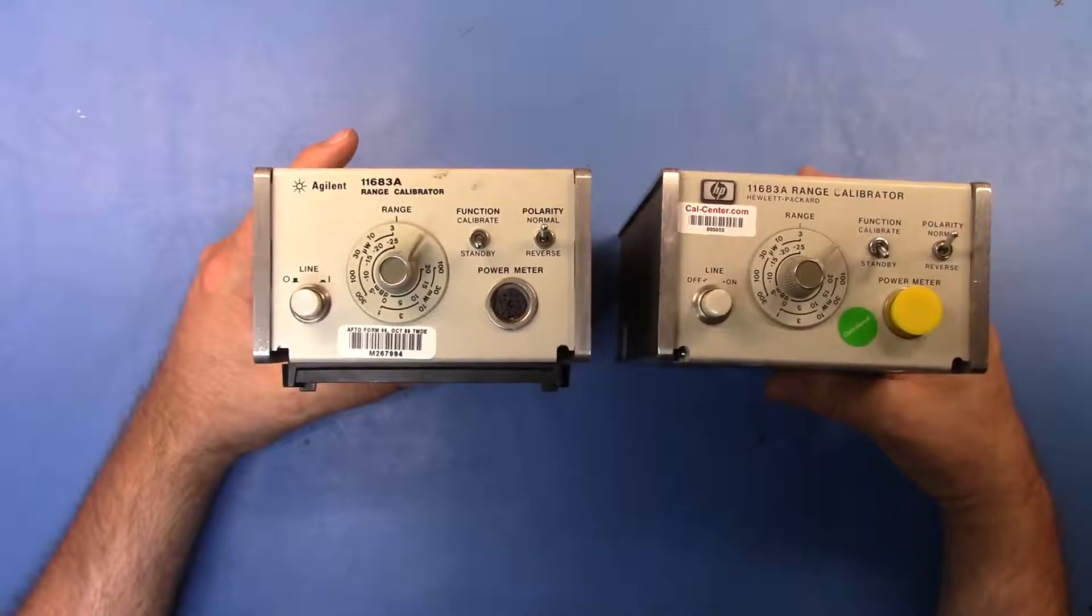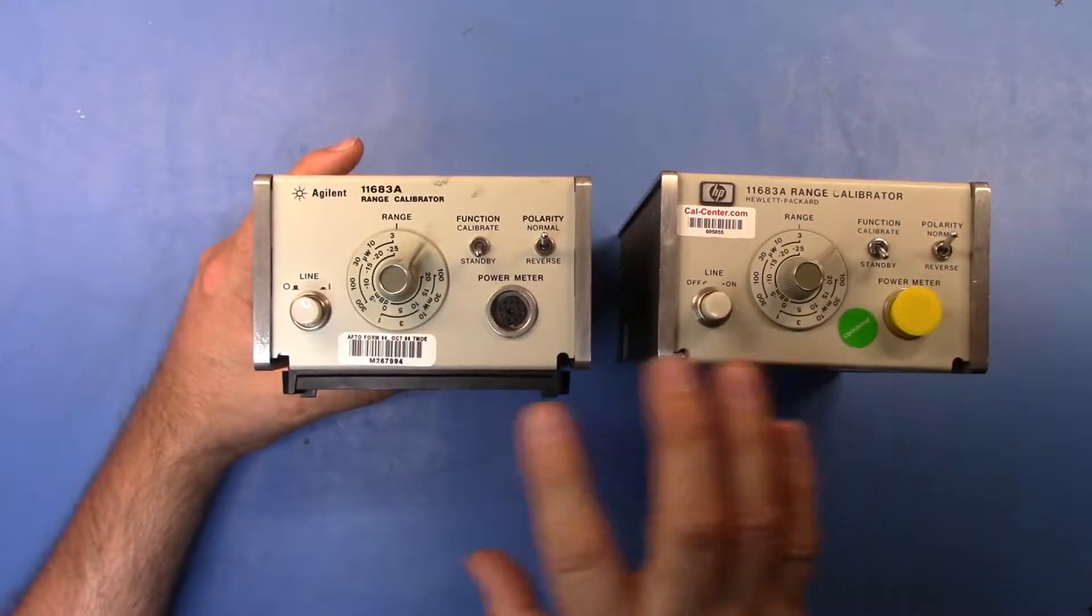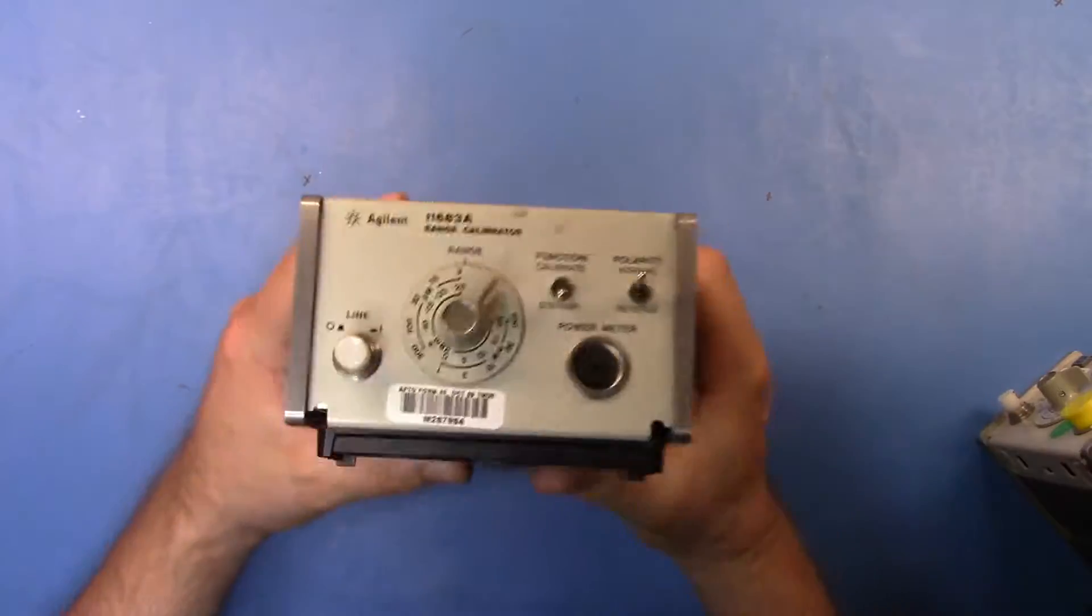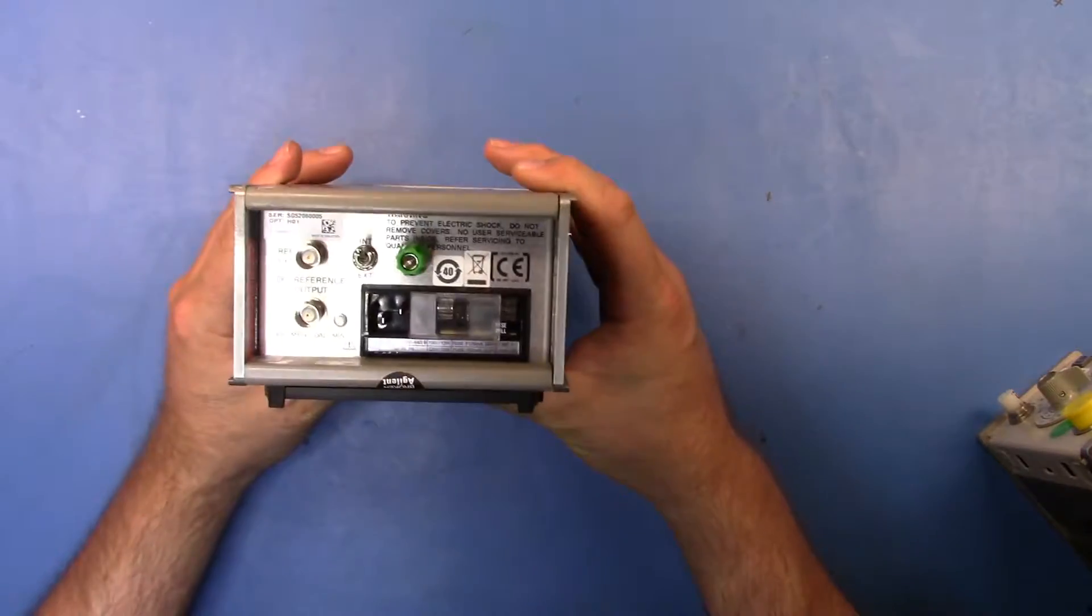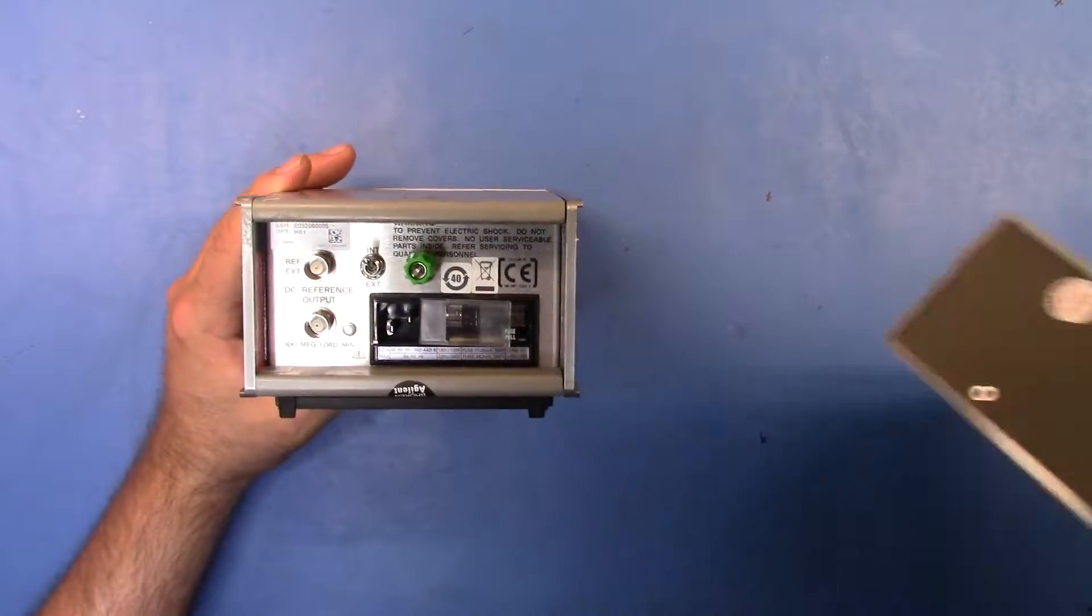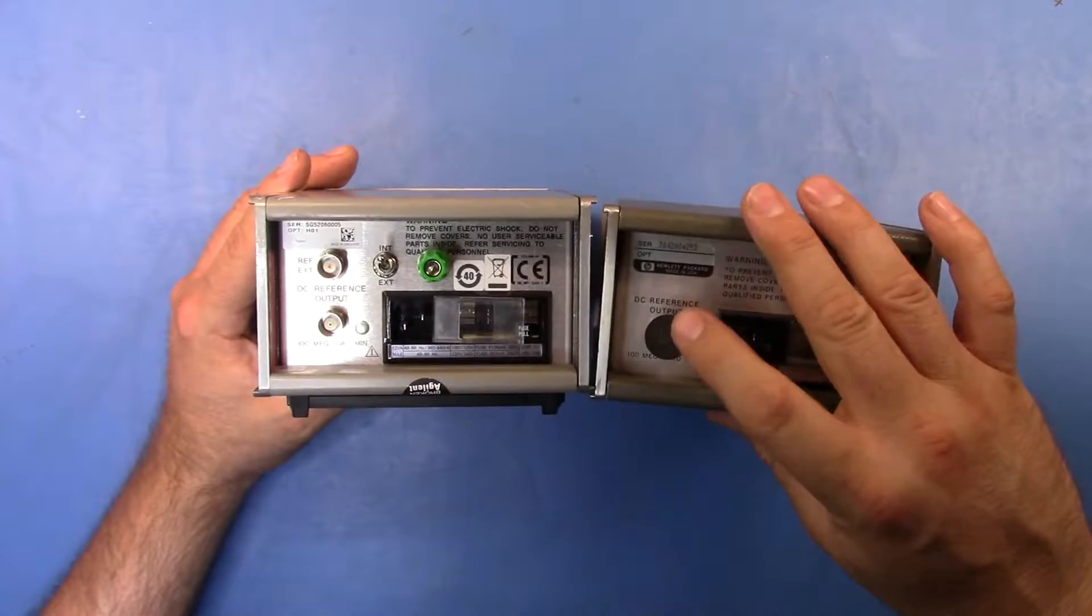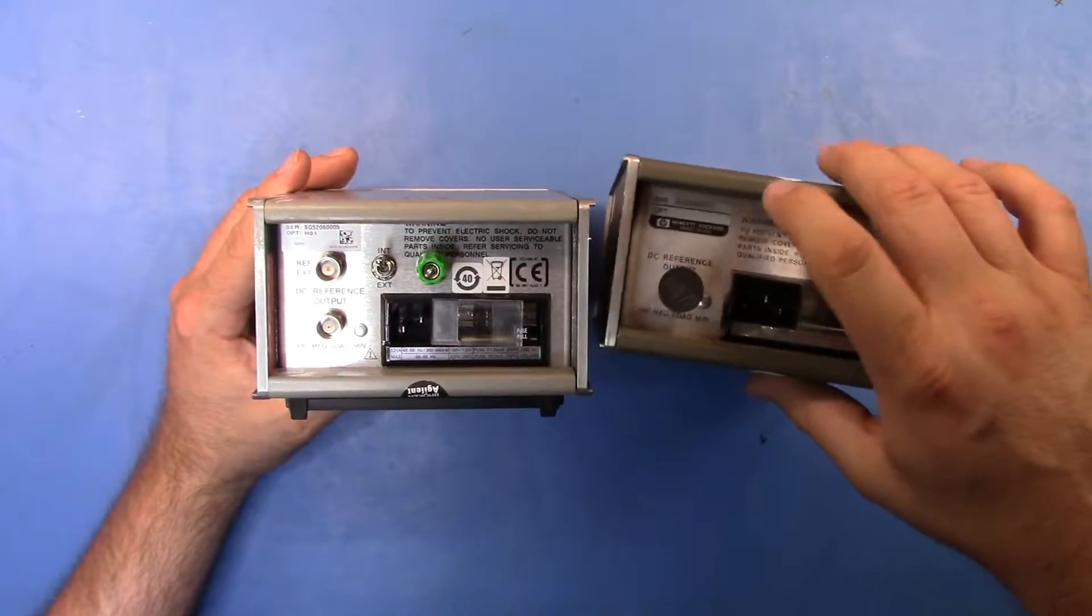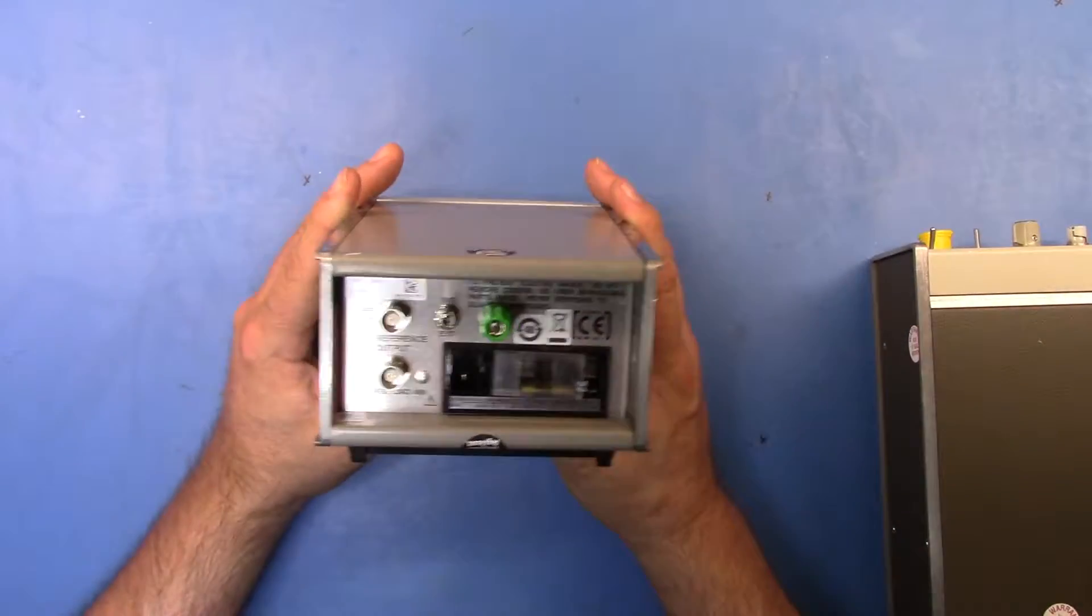The one that I've been previously using is branded Hewlett Packard, but it's fundamentally the exact same calibrator. So why did I invest in buying this calibrator from the Department of Defense? Well, the reason is on the back here. All we have is the DC reference out and we don't have any other componentry, but this guy here is the 11683 with option H01.